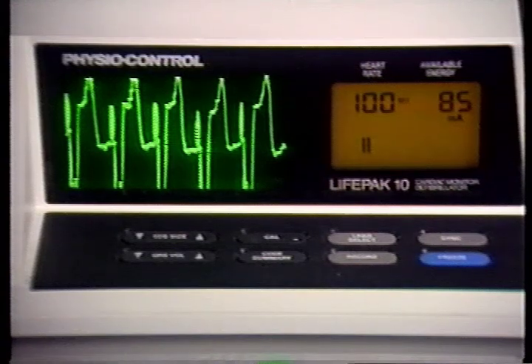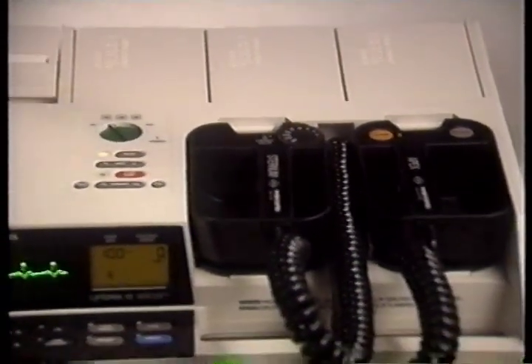During pacing, the patient should be observed at all times. Conscious patients may complain of discomfort. Analgesia and/or sedation may be needed. To terminate pacing at any time, push the start-stop button. Pushing the charge button or selecting the paddles mode will also terminate pacing. If the patient requires defibrillation during pacing, select energy and push the charge button. The pacer will automatically turn off and the defibrillator will charge to the selected energy level. Defibrillate as described previously. Do not place defibrillator paddles over pacing electrodes. Doing so could present a fire hazard.